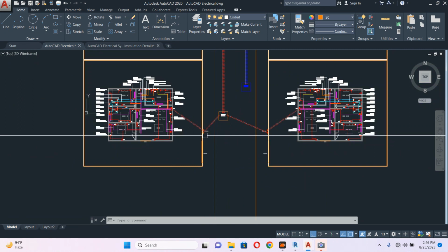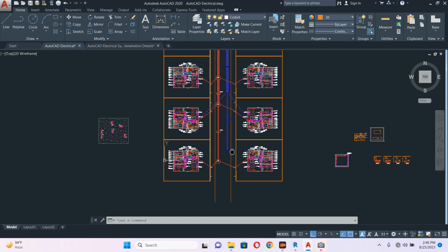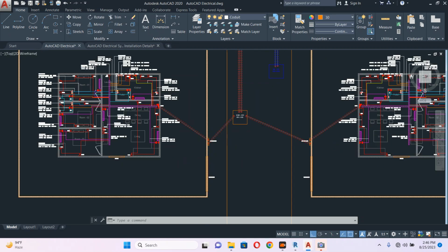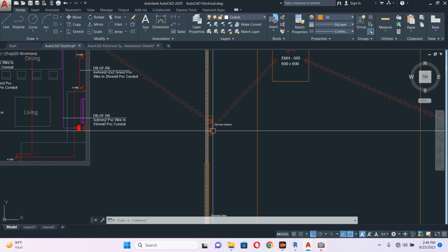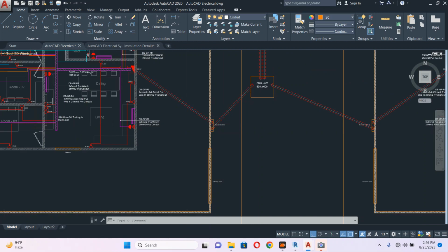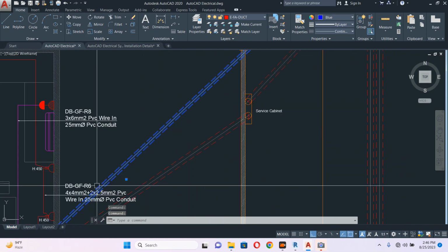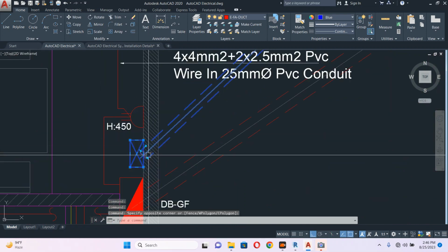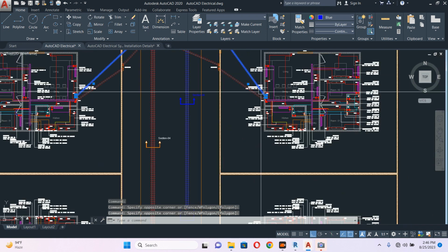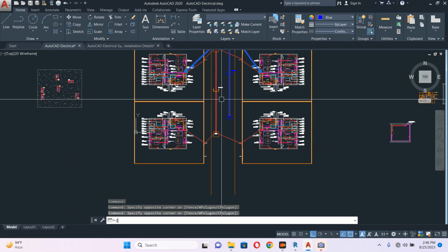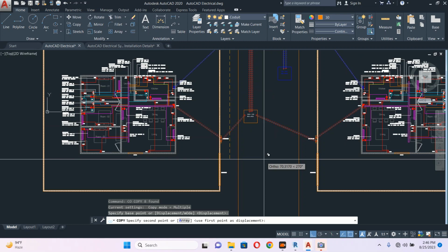So this one should be wrong. Why? No, this one is not wrong, because here we are terminating. This is okay, because this is a single cable. We are terminating here, so it can go like this. So this is how it will work. Let's make more telephone junction boxes. Another thing, you have to coordinate this one with other services also. Now I have mentioned only 2 services.